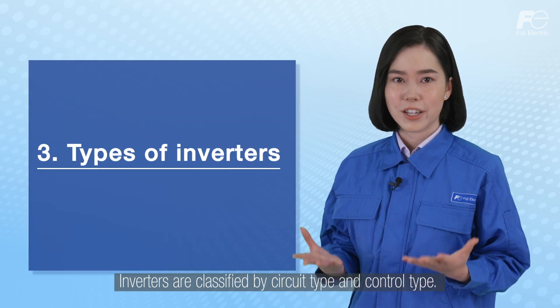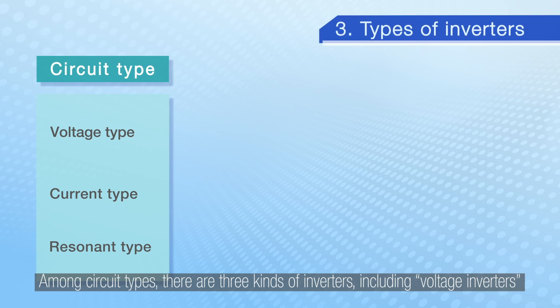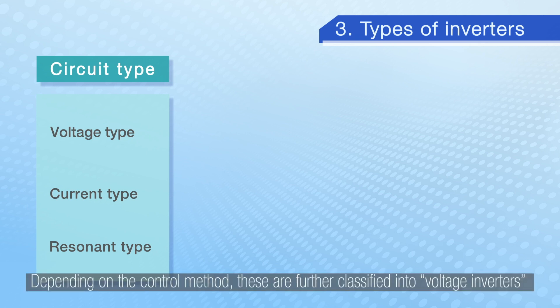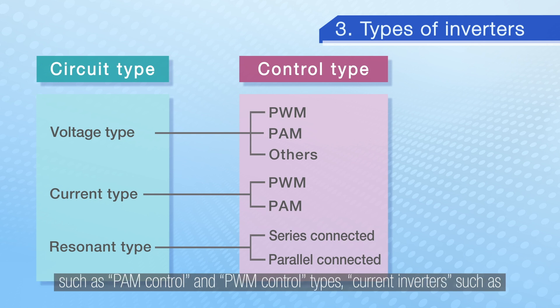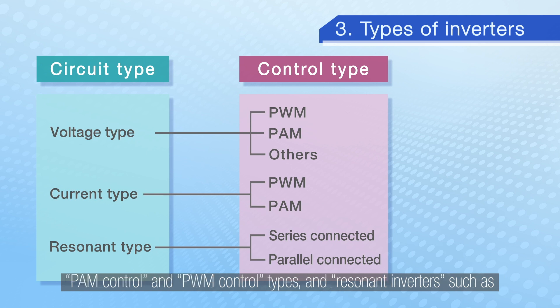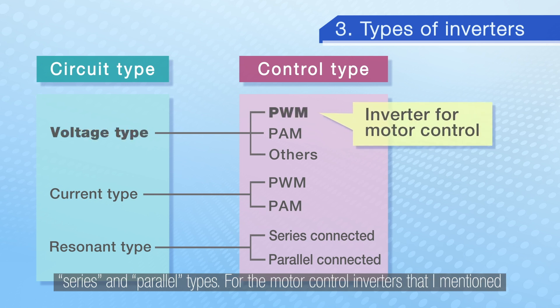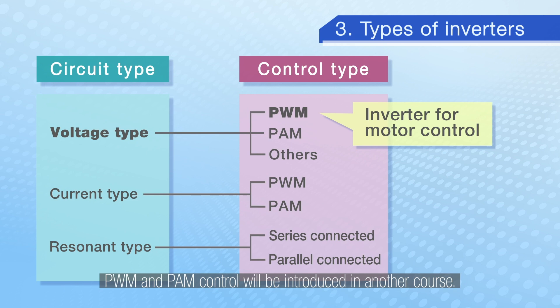Inverters are classified by circuit types and control types. Among circuit types there are three kinds: voltage inverters that output voltage, current inverters that output current, and resonant inverters. Depending on the control method, these are further classified into voltage inverters such as PAM control and PWM control types, current inverters such as PAM control and PWM control types, and resonant inverters such as series and parallel types. For motor control inverters, these applications use a PWM control type voltage inverter. PWM and PAM control will be introduced in another course.